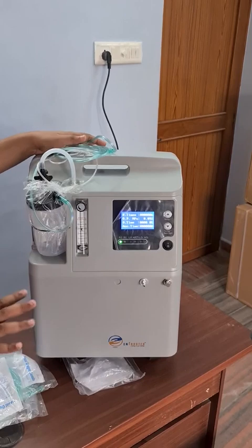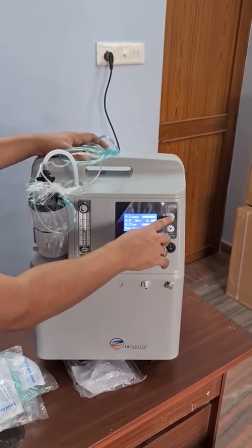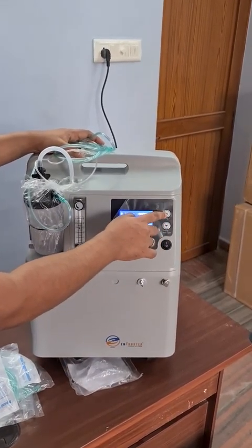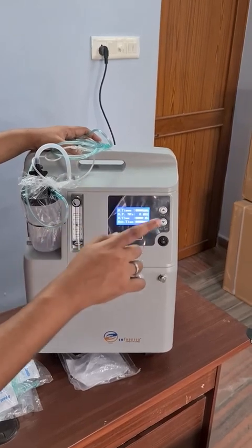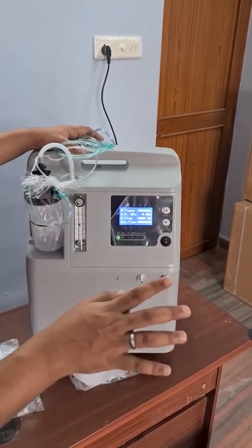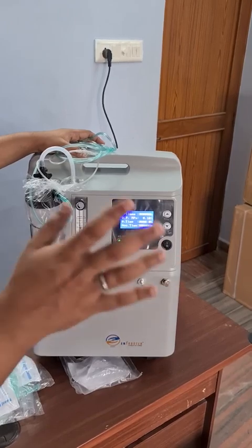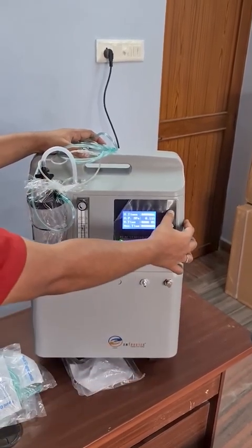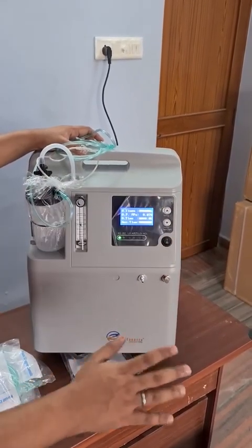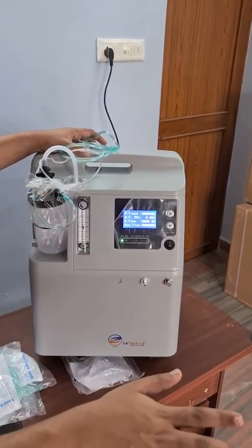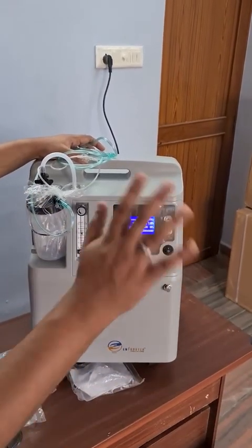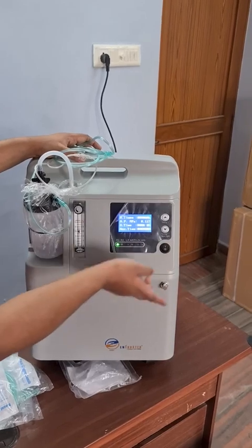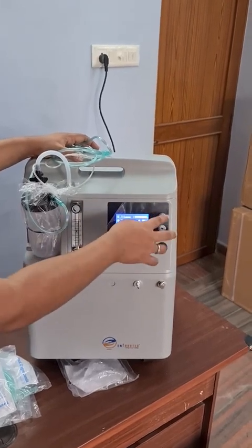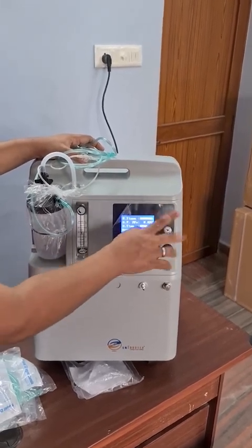And in case you want to use the timer function, you need to press the upward arrow, and each time you press the timer button, the timer will get activated by 10 minutes. Say for example, if you want to set the timer for 1 hour, you press the up arrow 6 times. Then exactly after 1 hour, the machine will get switched off. And once the machine is switched off, in order to switch it back on again, you need to power off and power on. So it's up to you whether you want to use the timer. So this is for the backlight.